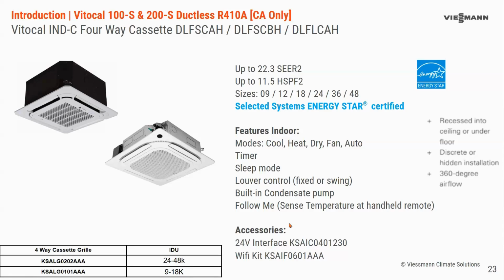There are cassette grills that can be ordered separately. We also are working on a kitted number to have them all come together with the cassette grill. But just be mindful, depending on the way you order the product, you can order it separate or as a kit. And there are 2 different grill part numbers. For 9,000 to 18,000 BTU it is a 2x2, and then from 24 to 48,000 it is a 3x3 grill. Wireless control is standard. Wired control is optional. So every indoor unit that has a receiver for the remote control that is visible or accessible will come standard with the wireless, and optional will be the wired.